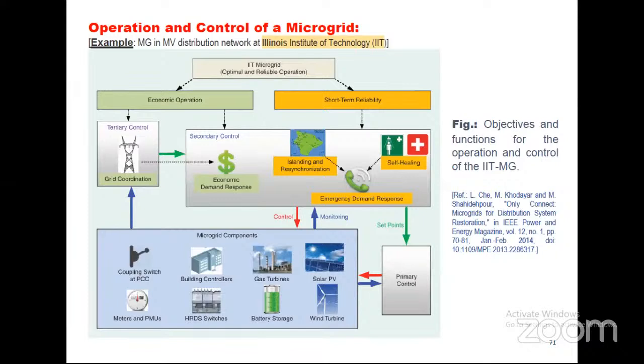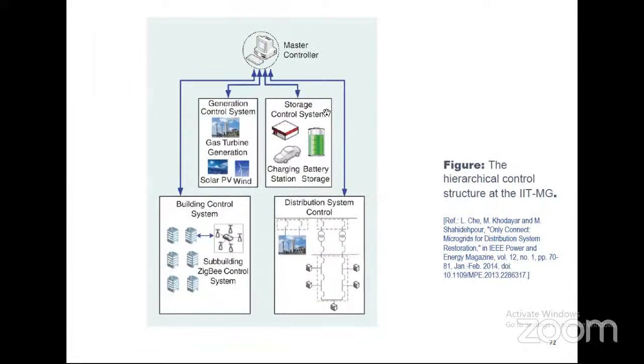This all happens in real time. All these controls are integrated, and the building controllers facilitate energy management by reducing or shifting different loads at different locations according to modes specified by the main operator. So it may operate in both islanded and distributed modes. In island mode, there is a provision of natural gas turbine and battery storage system that maintains rated frequency and voltage through primary and secondary control functions, since tertiary control is not available at that stage.